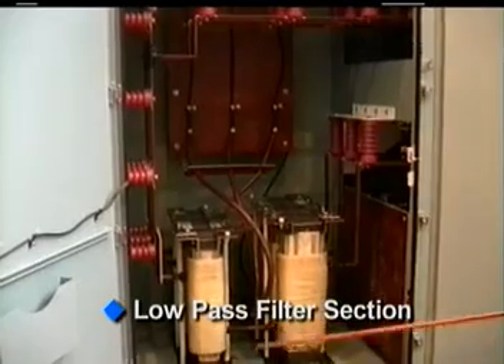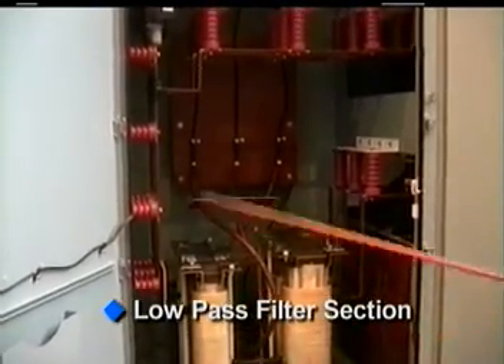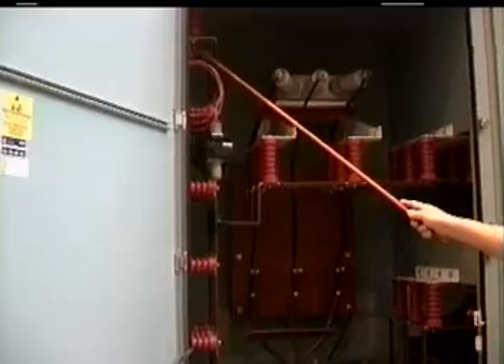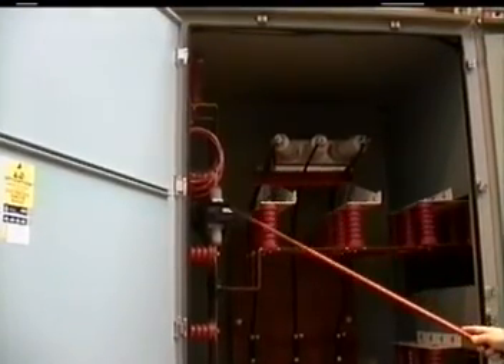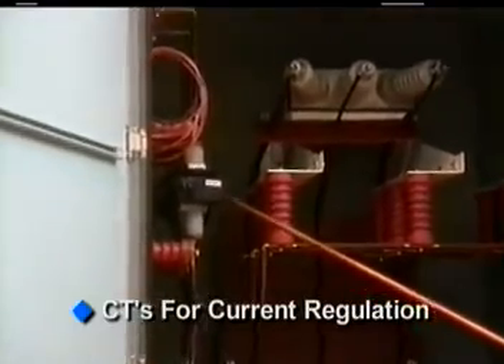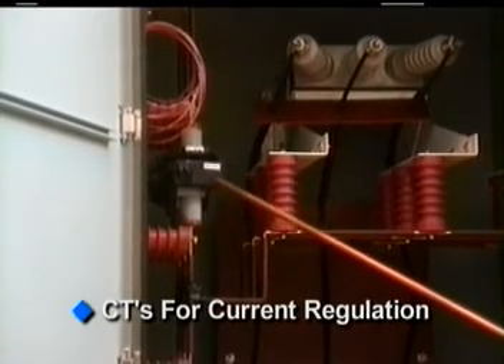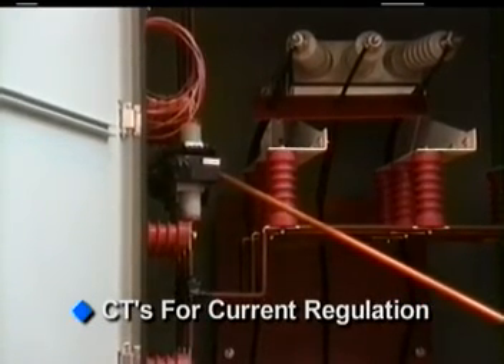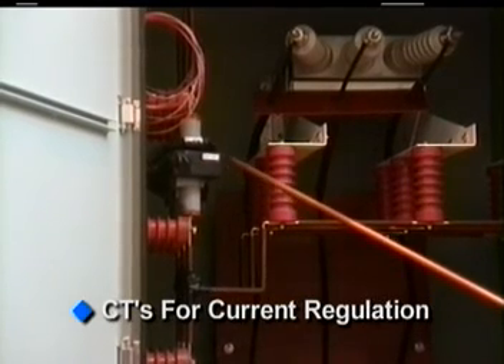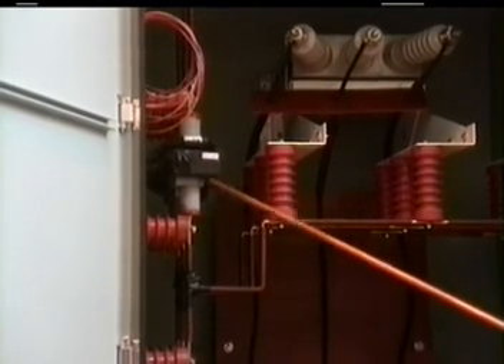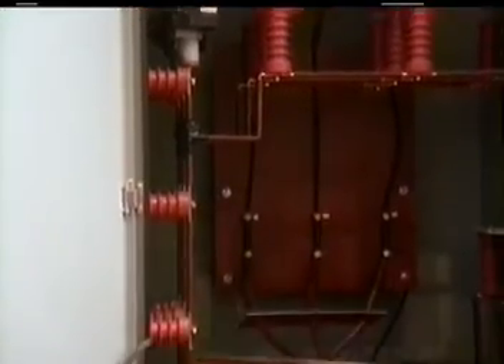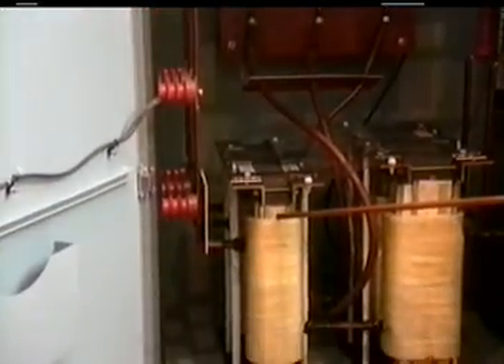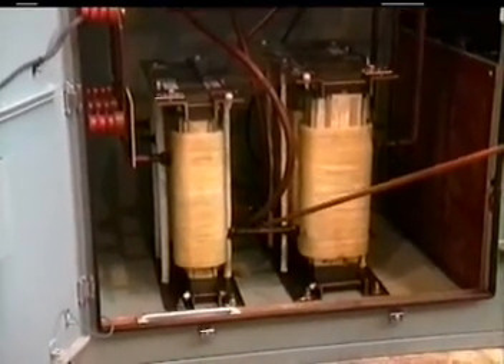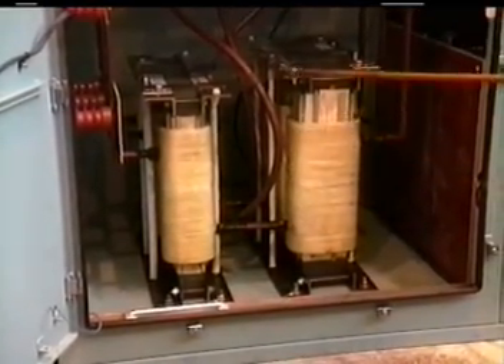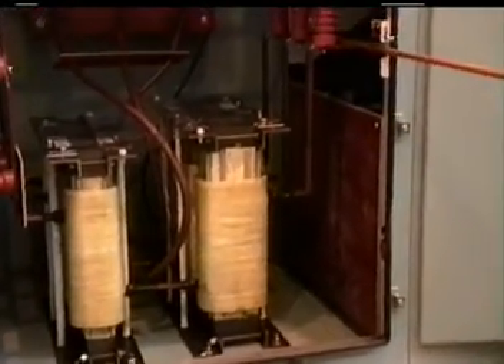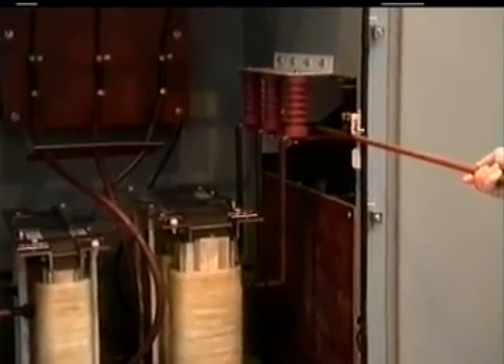Next to the disconnect section is the input filter section of the starter. We come out of the top of the disconnect section here, come down through the CTs. There are 2 CTs per phase. In the system, 1 CT feeds the Multilin for motor protection. The other CT feeds the solid-state starter section for current regulation. We come down here through the insulated bus to the input reactor, and from the input reactor to the output reactor, and from the output reactor we come along here to the inline bypass, the inline vacuum contactor.